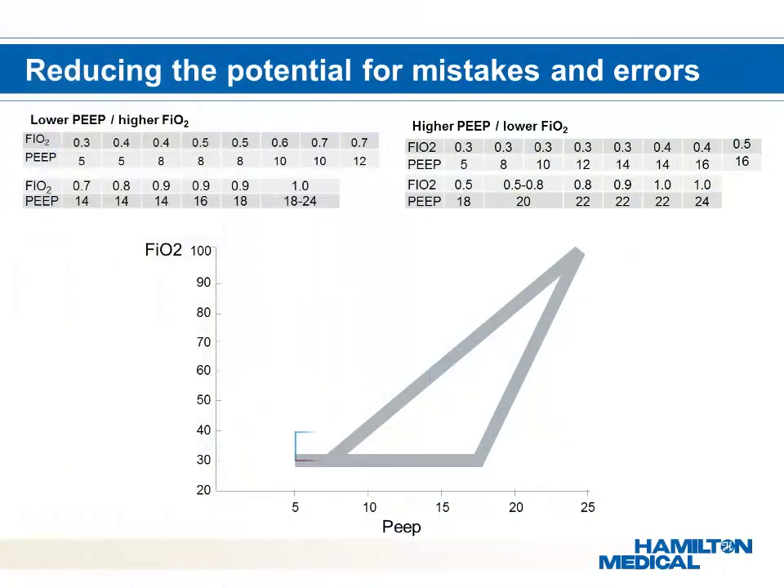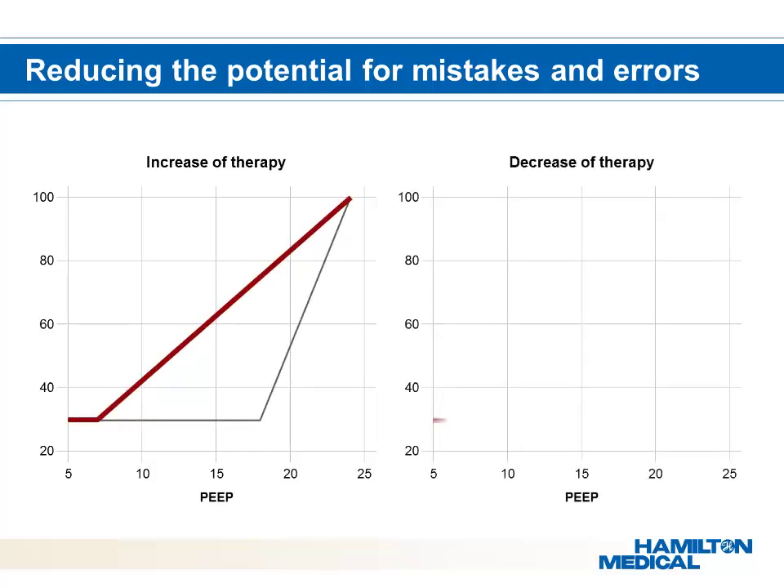Studies of the ARDS network tables have been summarized and used to create the working principle for IntelliVent ASV. In the case of desaturation, the ventilator will optimize SpO2 by adjusting FiO2 and/or PEEP depending on where the patient's FiO2 and PEEP fall in the table. IntelliVent ASV algorithms follow two commonly used guidelines: ARDSnet for increasing therapy and the open lung concept for decreasing therapy.